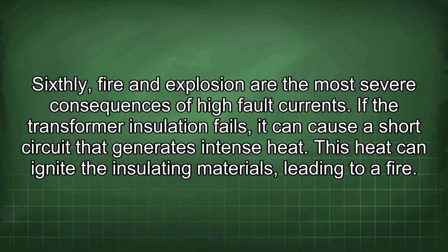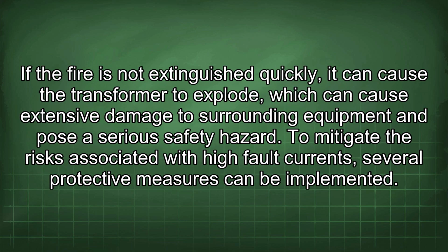Sixthly, fire and explosion are the most severe consequences of high fault currents. If the transformer insulation fails, it can cause a short circuit that generates intense heat. This heat can ignite the insulating materials, leading to a fire. If the fire is not extinguished quickly, it can cause the transformer to explode, which can cause extensive damage to surrounding equipment and pose a serious safety hazard. To mitigate the risks associated with high fault currents, several protective measures can be implemented.